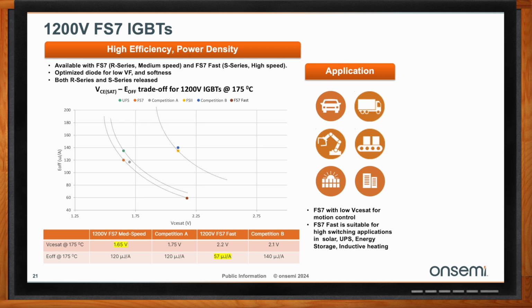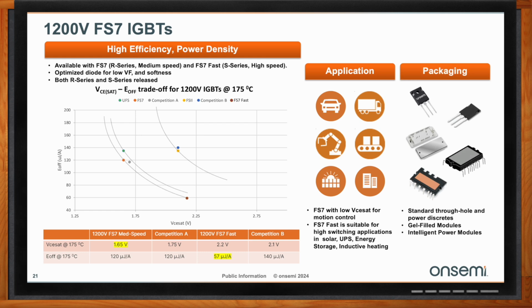These are optimized for lower VCE sat, which is sort of the analog to your RDS(on). If you have lower VCE sat, these perform better with conduction losses in motor control designs. Your switching frequency is on the order of roughly 20 kilohertz, though it varies, especially with a variable frequency drive, but that's the middle range you'll typically see.